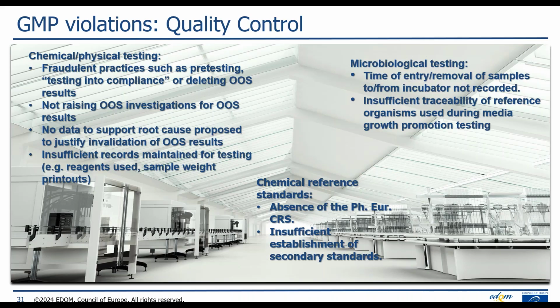QC. Okay, yeah, fraudulent practices, testing into compliance, deleting OOS results. Again, I still saw it 2 weeks ago, that HPLC series injections were repeated and the OOS one ignored, not reported. Insufficient records, reagents used, sample weight printouts. This got better. Microbiological testing, time of entry and removal of samples from the incubator not recorded, insufficient traceability.